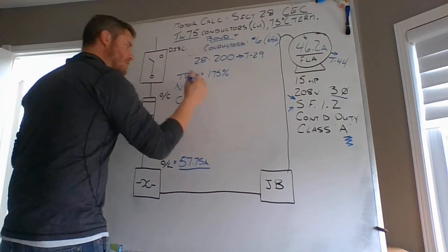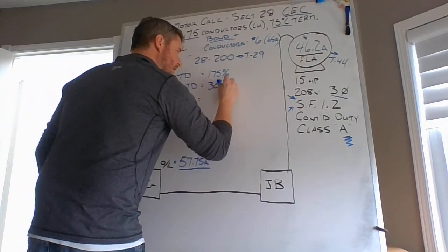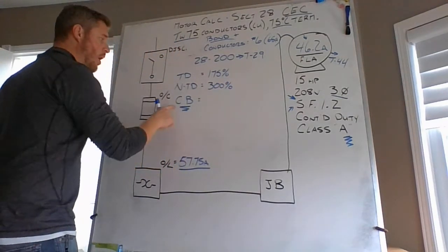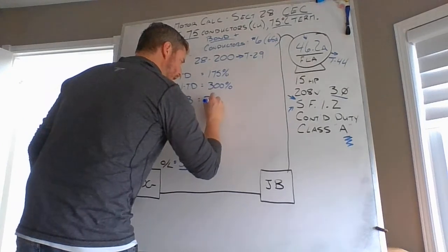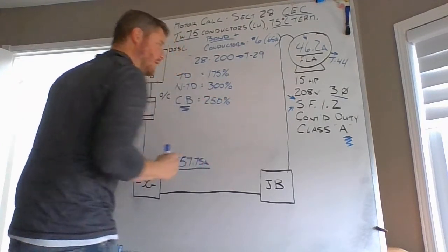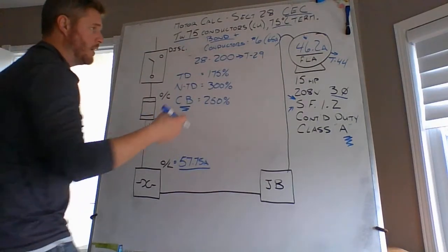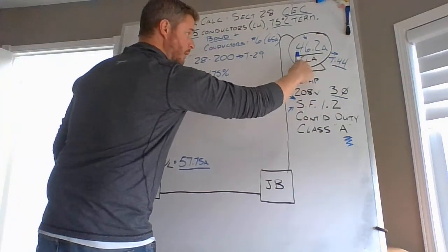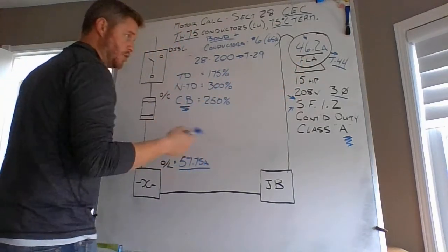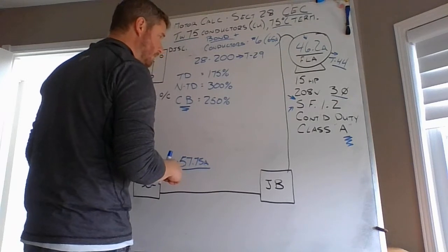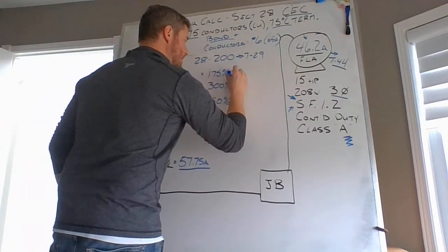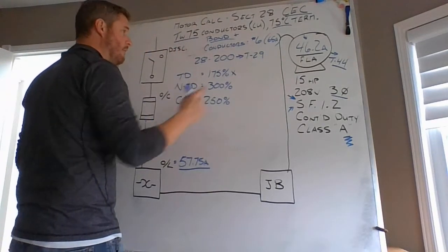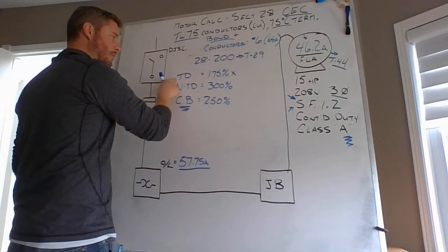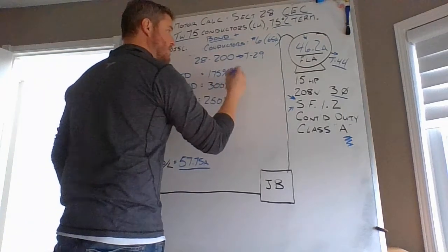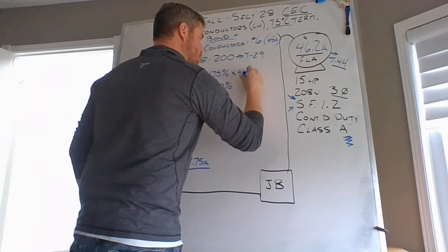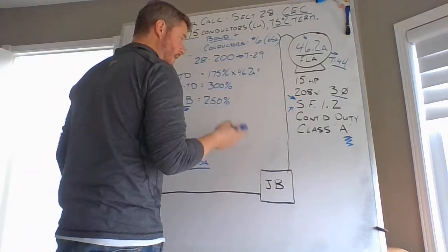Your full load current ampacity of your motor. For a non-time delay fuse, you're looking at 300%. Your full load current ampacity of your motor. Or for a circuit breaker, you're looking at 250%. Your full load current rating of that specific motor generated from, once again, table 44. That's exactly where we came up with the FLA for this 15 horsepower, 208 volt 3-phase motor. So I can observe my 175% of my full load current rating to properly size a time delay fuse. So I would take 175% times 46.2 amps and come up to a maximum value.